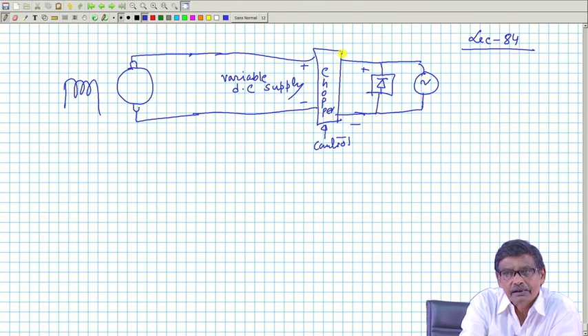In this scenario, you can easily see you do not require any starter. A 3-point bulky starter is not necessary. Why was the starter necessary? Because you are applying full rated voltage and armature resistance is small. Therefore, you incorporate some resistance in the armature circuit like a 3-point starter, then gradually cut it out and apply rated voltage. But here, if I start applying the voltage across the armature from a very low value slowly using this control, then there is no question of high current inflow into the armature. Go on increasing the applied voltage, speed will smoothly increase and finally settle down. Therefore, armature voltage control is a very popular method, not only for controlling the speed, but also for this.